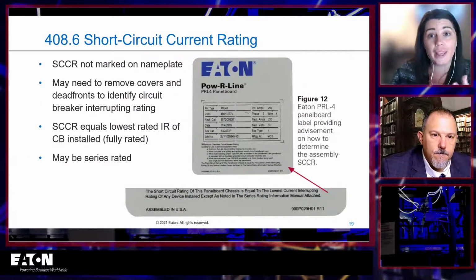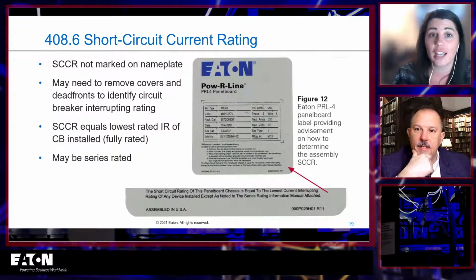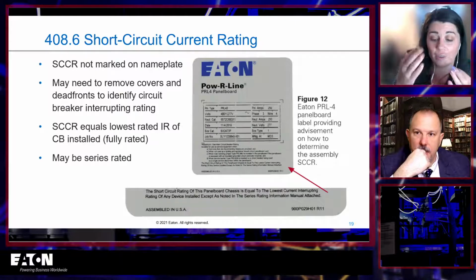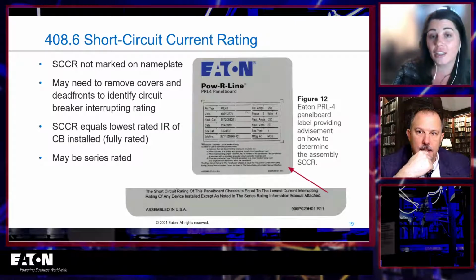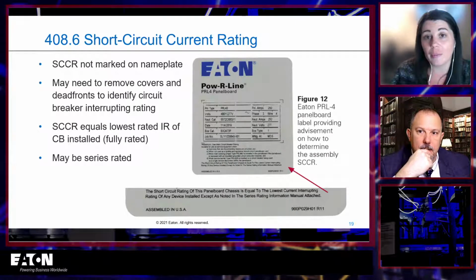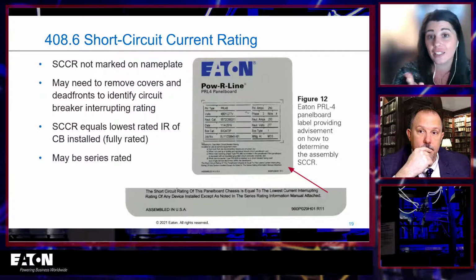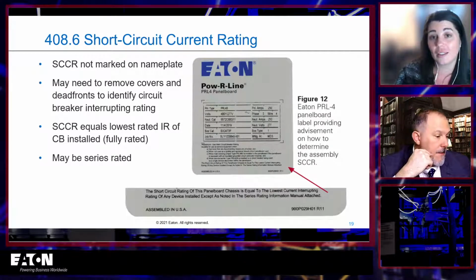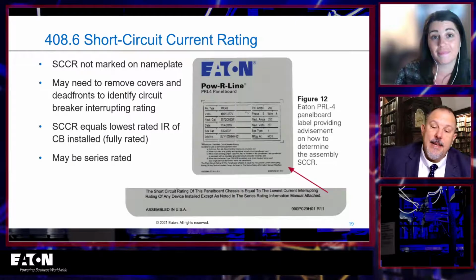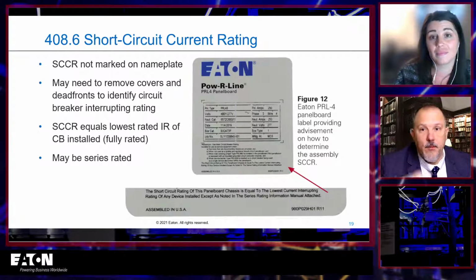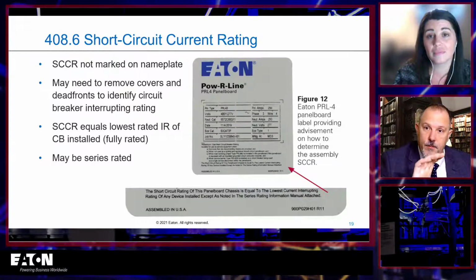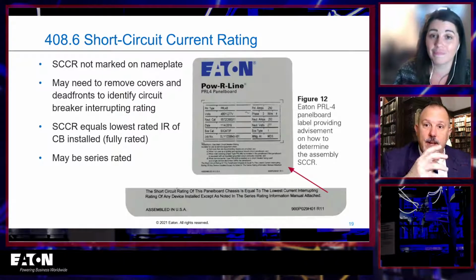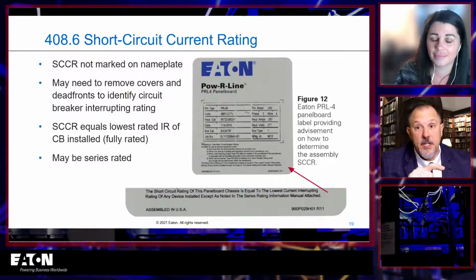And it can be a pain for inspectors to actually figure this out, because sometimes that information is hidden by a cover. You have to actually take off some of the dead fronts in order to identify it. But you don't have an SCCR written on your panel board because it is just equal to the lowest interrupting rating. And in some cases, the interrupting rating is not visible from the front. You've got to take the breaker out and look on the side, especially the miniature ones.